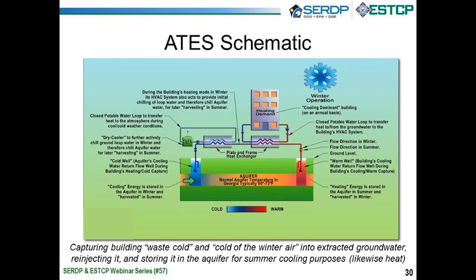That gets injected down into the cold well, and it begins to dissipate out into the formation, on the order of 5 to 10 million gallons per year for this building. That is our cold reservoir, and we're building up our cold storage all winter to use the next spring, summer, and fall. Later on, it warms up and we can't use the economizers anymore. We pull the cold water out of the ground, and typically the dry cooler is off. The building now dumps its heat into the water, and hence the creation of the warm well. So that's the basic schematic of what one of these systems would look like.